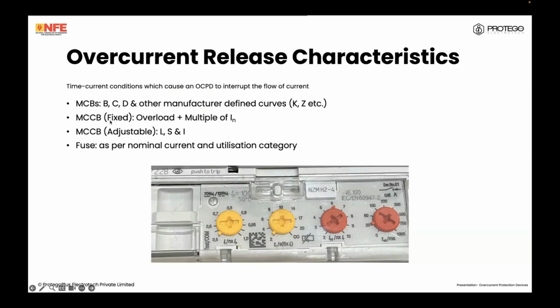For a fixed MCCB, it will be a certain overload current and a multiple of In, say 8 In. So for a 40 ampere, 320 amps would be the instantaneous tripping current. Then for an adjustable MCCB, you have something called L, S, and I. You also have G and all that, but we'll only look at L, S, and I.